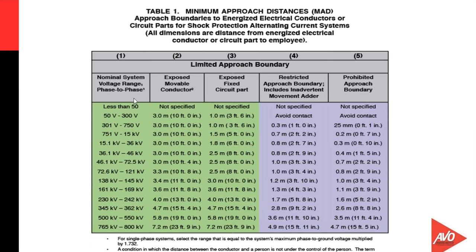If you look on the right side in the somewhat blue area, you'll see that there's a restricted approach boundary, and we also kept the prohibited approach boundary here in this presentation, because that becomes what's normally called the guard zone or the flashover zone. So even in a test area where you have all qualified workers, this prohibited approach boundary has to be adhered to, because if you get inside that, you may well actually create a flashover. Another issue with that is making sure that the test specimen is secured and is not adjacent to any grounded parts or anything like that within that prohibited approach boundary that possibly would cause an additional flashover.